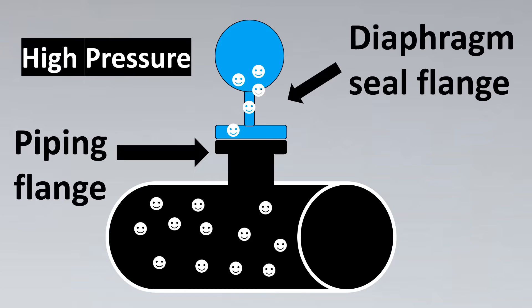Once they get inside, the pressure is not that high as compared to what is in the service. Because of this, these molecules recombine inside the diaphragm and stay within as H2 molecules, and now they can't come back to the service. For such cases, our readings in the diaphragm seal would be wrong, and this is a harmful scenario. But how can we avoid this?